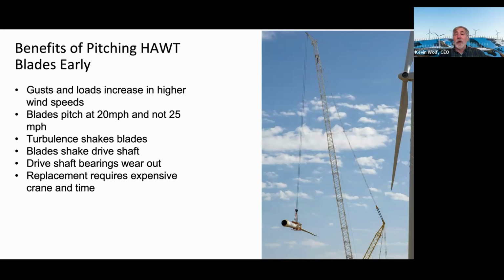Therefore, horizontal axis turbines have this problem. They want to keep the wind farm at 100% capacity. To do that, they need to keep their blades unpitched until they reach rated power, the wind speed at which the generator is maxed out. Once it's maxed out, the blade pitches so it doesn't overstimulate or produce too much energy for the generator. If you pitch it early, you lose power, but if you keep it too long and a gust comes, you've got a repair problem.